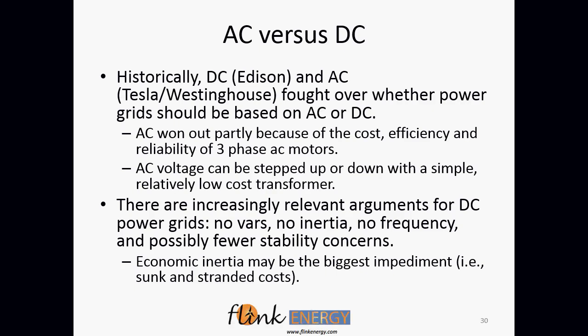The other advantage of AC is that you could change the voltage. Remember that the heating losses, the Joule losses, the I squared R losses in a power line are proportional to the square of how much current is going through it. So the more current you send through a power line, the more the losses are, and it's not linear, it gets really bad really fast. So if you're going to send a lot of power down a line, to avoid those losses, since power is voltage times current, you want the voltage as high as you can get it, so the current is as low as possible. Does that make sense?